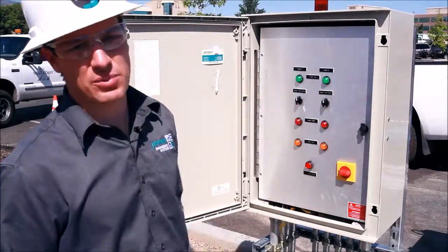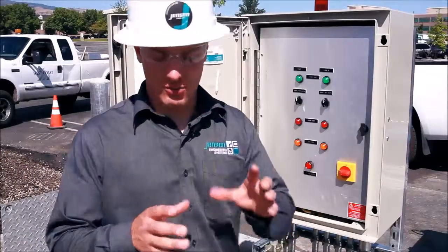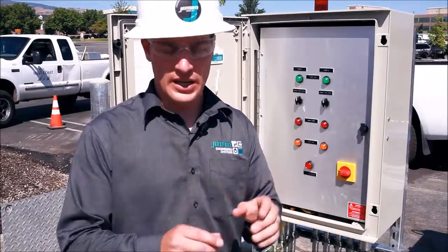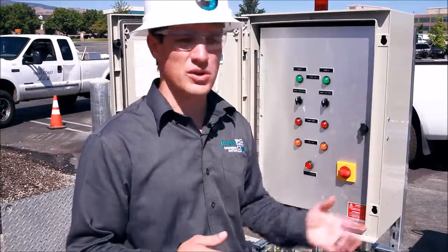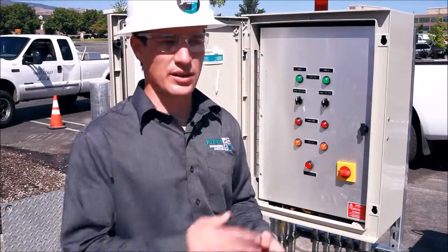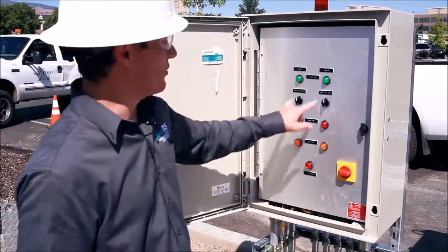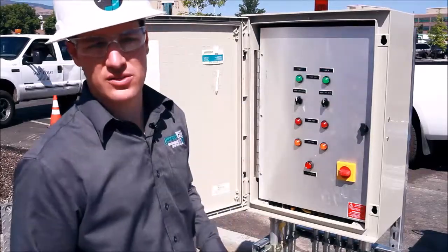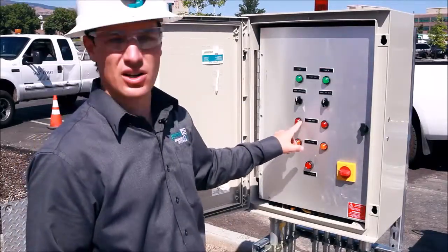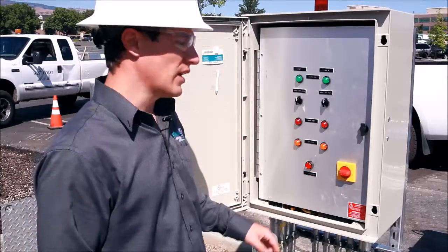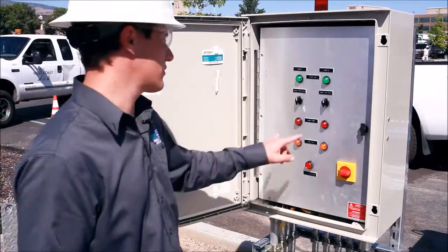Moving down, we have our overtemp lights. So inside the motor of the submersible pumps is a thermal switch. If the motor was to overheat, the switch would open, break the continuity of that line, and it would tell the PLC that the thermal has overheated, and from there it would sound an alarm telling you that you have a thermal overheat, and that you probably need to check out your pump and possibly service it.